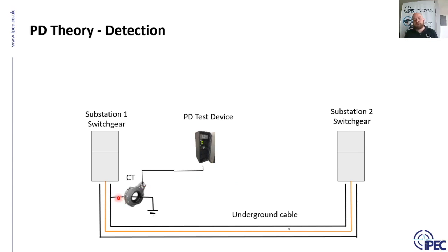Now, detecting PD on the earth sheath, the earth must be isolated from the switchgear. If the earth is not isolated from the switchgear, the PD signal will enter the switchgear and be lost. So it's important for the earth to be isolated from the switchgear. Now, when it comes to the lower end of the medium voltage, maybe 11 kV, 10 kV, whatever the standard is in your country, sometimes this may not be the case.